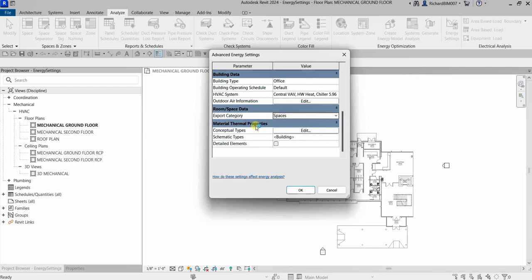You can also specify the Material Thermal Properties of your building. There are three ways to do this: Conceptual Types, which is the default; Schematic Types, which when enabled overrides conceptual types; and Detailed Elements, which when enabled and thermal properties are specified for building elements, will override both conceptual and schematic type settings.